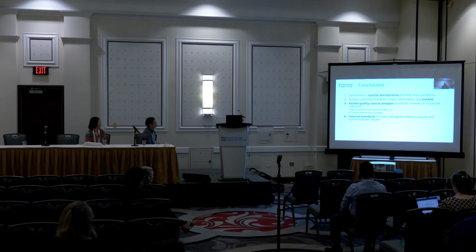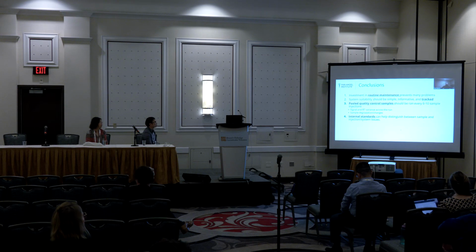Some conclusions that we can think about going forward: one, investing in routine maintenance really can prevent problems. The last thing that you want to do is just hope that your instrument's going to hold on for this one last study. You run it, and then the data looks like junk, and then you're going to have to clean it and rerun it anyway, and then the samples are older, and maybe you don't have enough to re-inject everything, and so on. So it's really good to stay on top of your preventative maintenance, and this keeps your average downtime over the course of the year as low as possible.